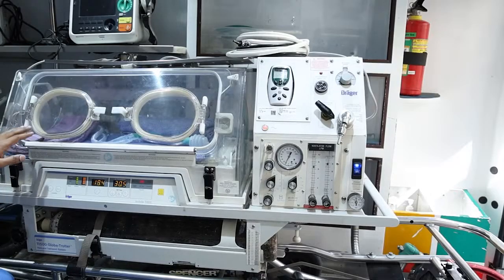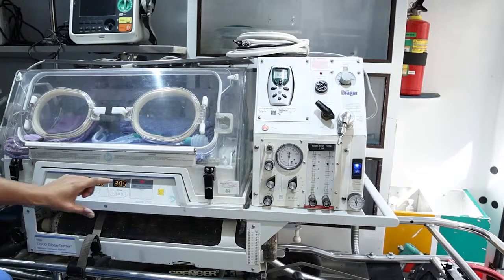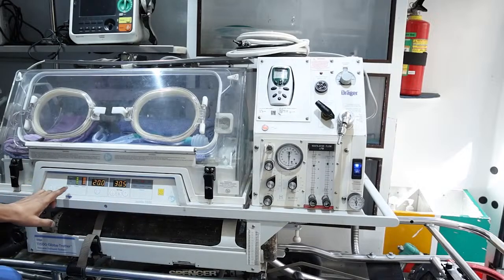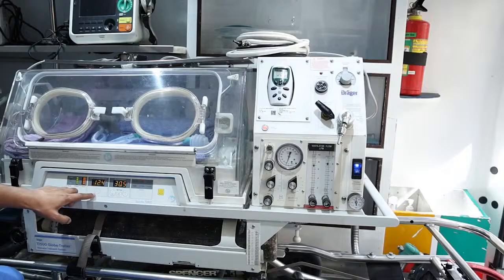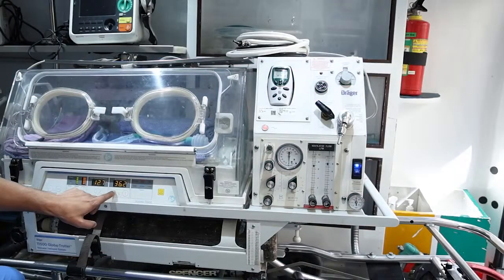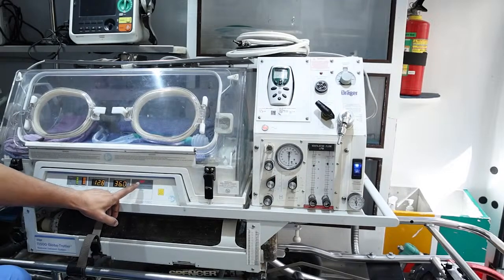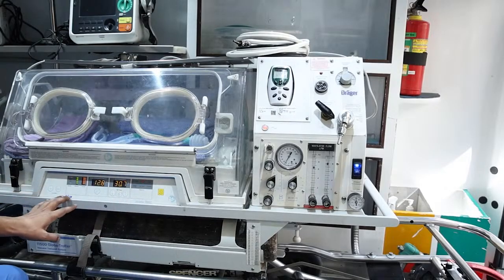So coming to the incubator per se, here the front panel shows the display where you can see the power mode, the battery life, and the heater output. There are two modes. One is the baby temperature monitor, where the exact temperature of the baby will be displayed here, and then the air temperature, which you can increase or decrease once it turns green. So here we have other parameters which show high temperature, power failure, sensor, heater temperature. The other alarms can be seen here on the display.